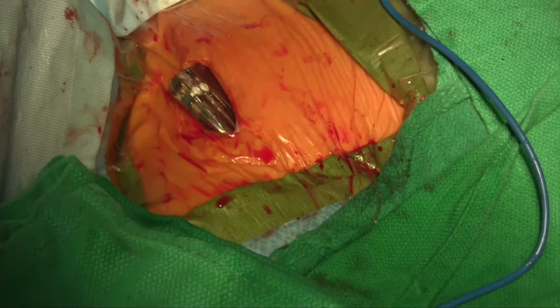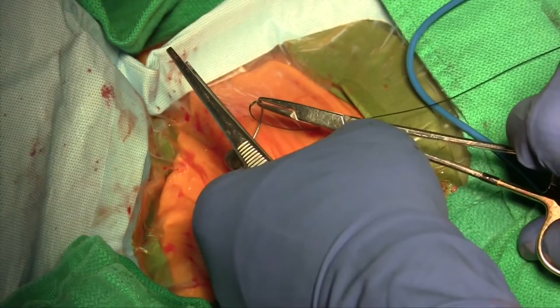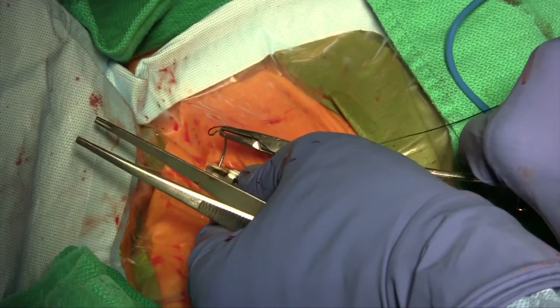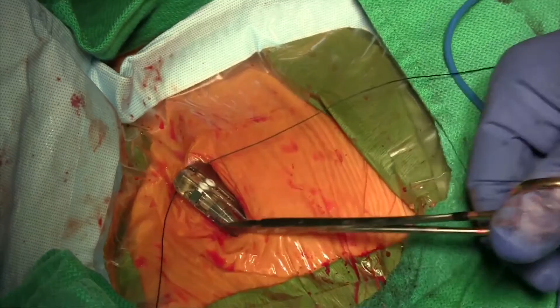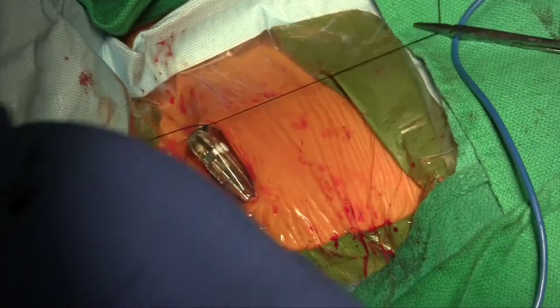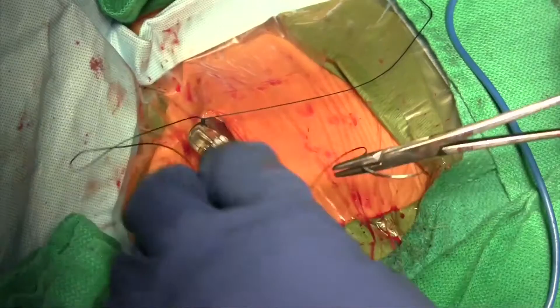Well, I will tell you, the volume occupied by the components inside is 80% battery. The smaller the pacemaker, the less longevity. The battery will deplete sooner. The bigger the battery, the longer it lasts. So they do have pacemakers and defibrillators that have larger battery capacities to allow the device to be lasting longer. Most people don't want to come in just a couple of years and have their generator replaced. They'd rather, you know, wait many years before that happens.